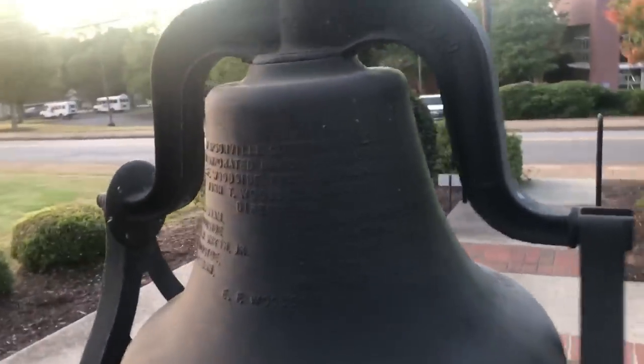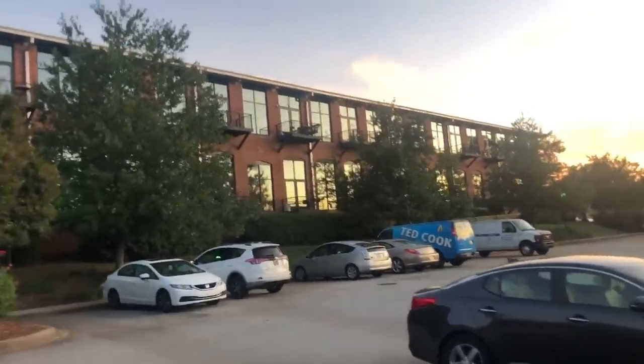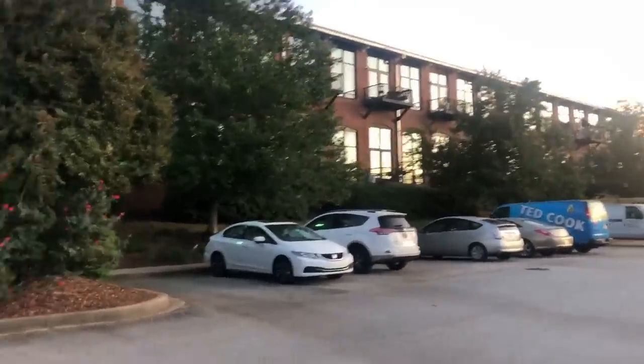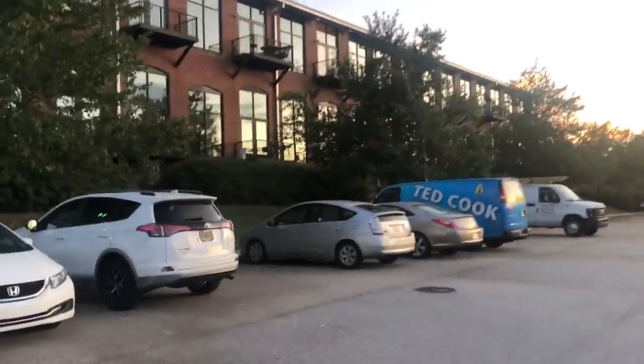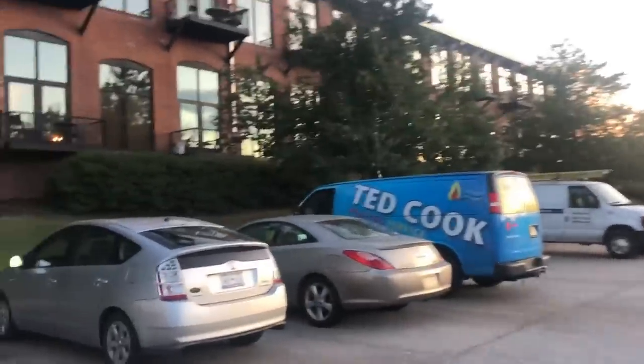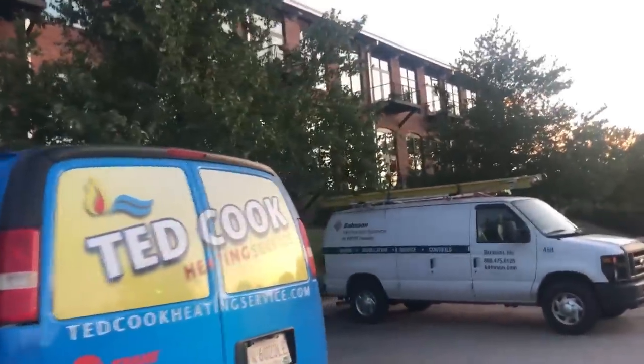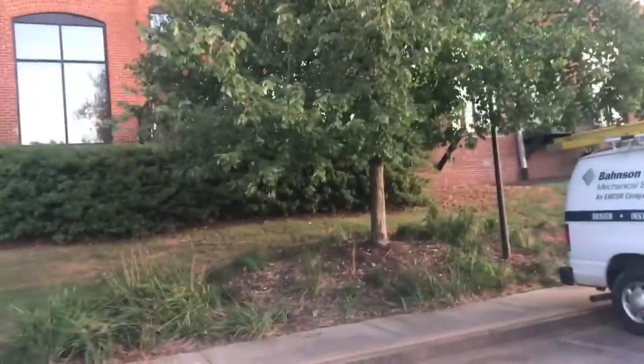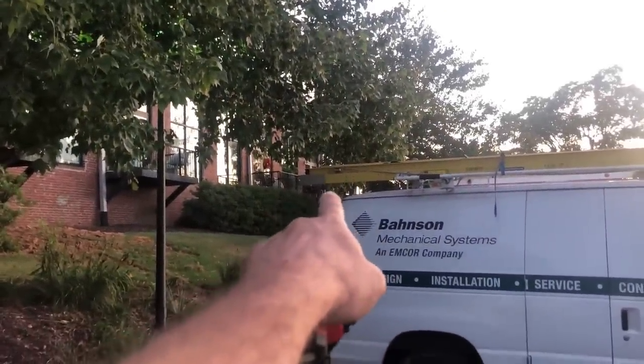For whatever reason, the city right next to us thought it would be real neat to take this old cotton mill and rehab it into condos. It is extremely difficult to work on four or five units sitting in clumps behind all those bushes — very few of them are numbered or marked. Hard to know which unit goes to which condo. I've been inside enough to determine we are getting no 24-volt signal to our outside unit, which is right here, but the condensers are on the far end of that clump behind those bushes.